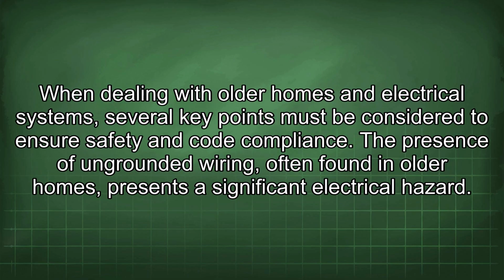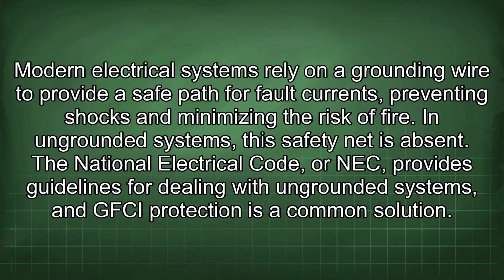When dealing with older homes and electrical systems, several key points must be considered to ensure safety and code compliance. The presence of ungrounded wiring, often found in older homes, presents a significant electrical hazard. Modern electrical systems rely on a grounding wire to provide a safe path for fault currents, preventing shocks and minimizing the risk of fire. In ungrounded systems, the safety net is absent.